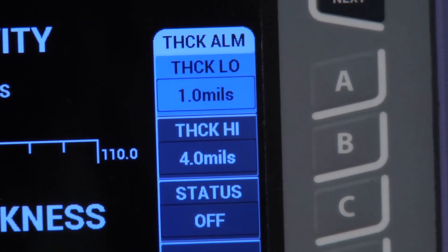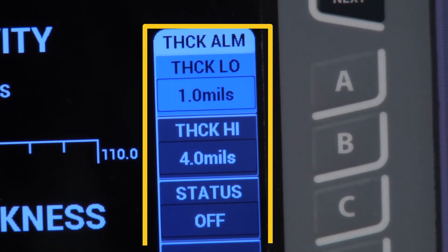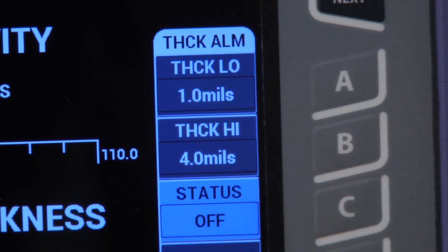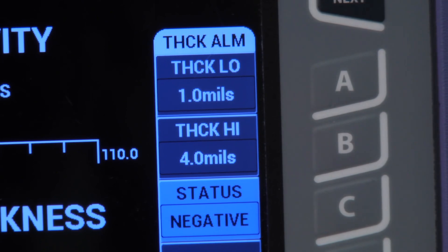Pressing alarm again brings up the coating thickness alarm. You can select the lower limit shim thickness using A and the upper limit using B. Set the status to positive or negative.